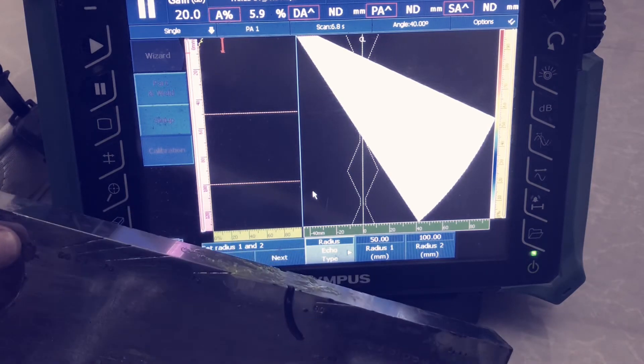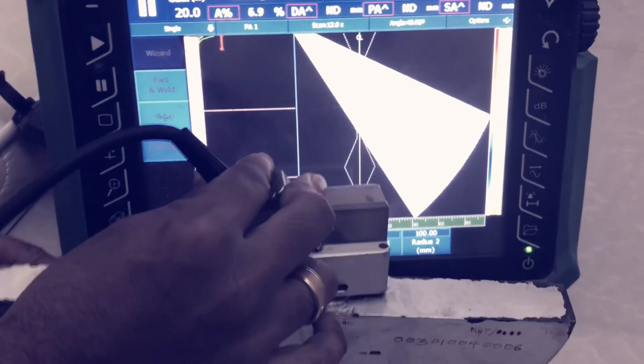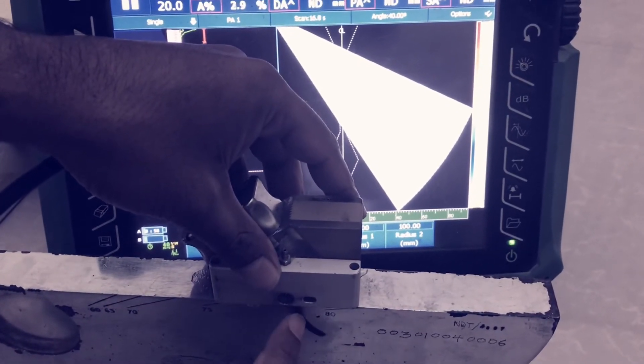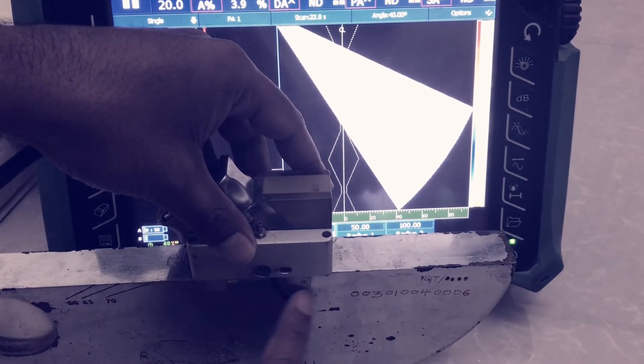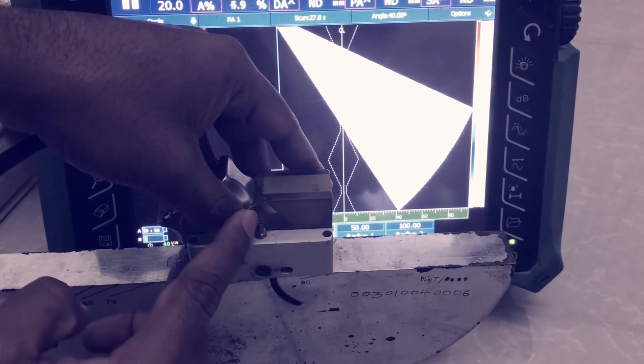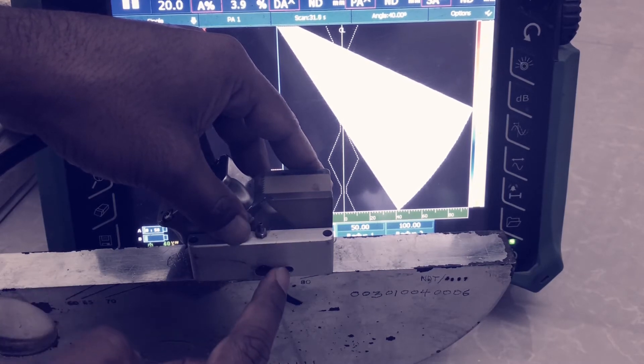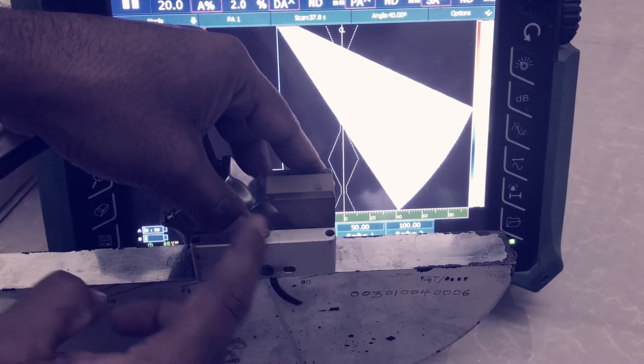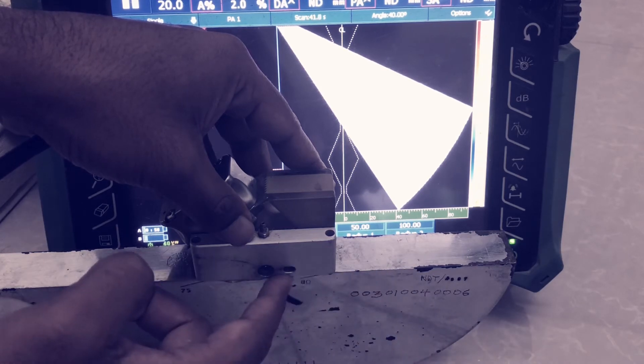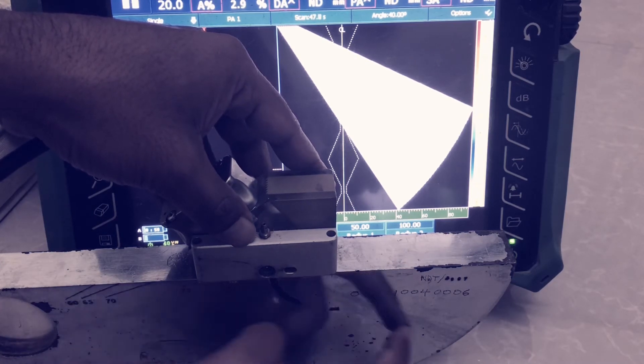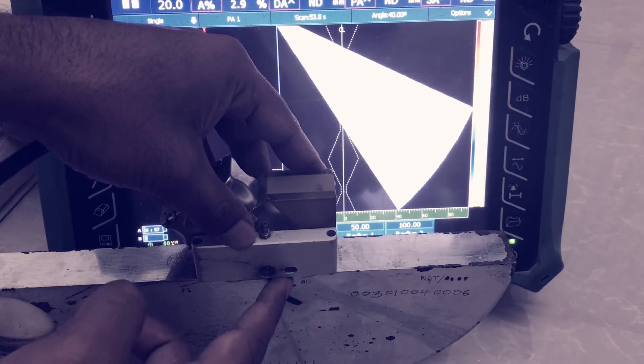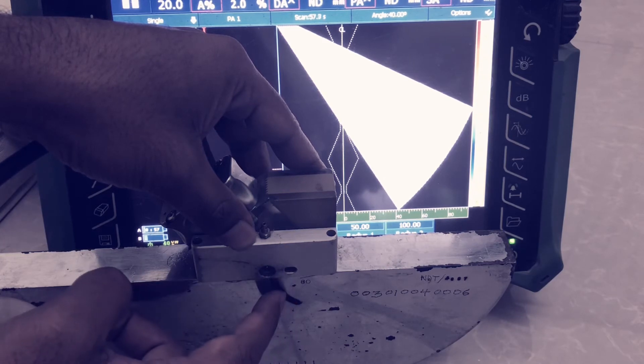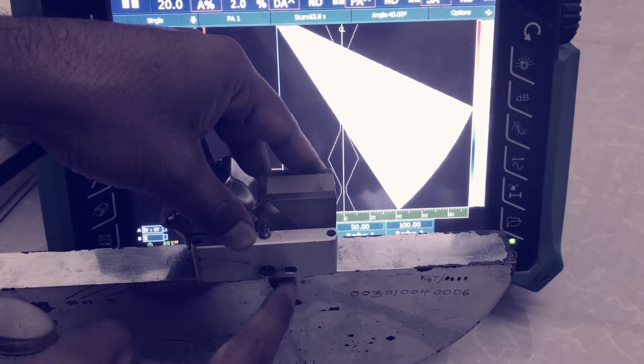Here you can see if you place the probe like this, it is firing from here. It is hitting here at 100, and it is reflected back. What's first echo from the 100, and again it is back here at 25 and reflects back here, but it will not receive. So again it will go here and return back. So the second echo will come around 225. If it is a slot, it will go like this. First echo will come from 100 and second one from 200 only. It's a slot. If it is a slot, first echo from 100, second echo from 200. Here it is 25 distance, that's why it is showing 225.